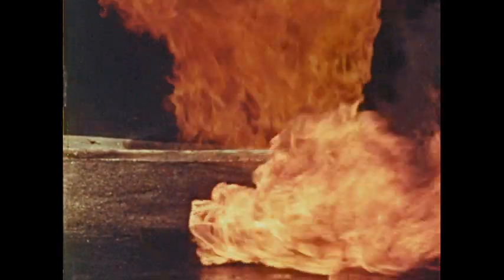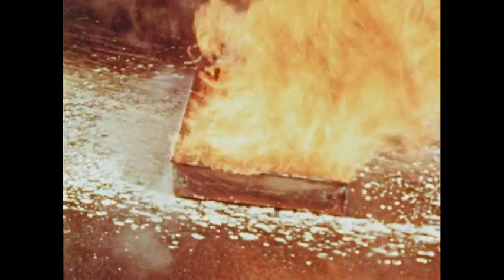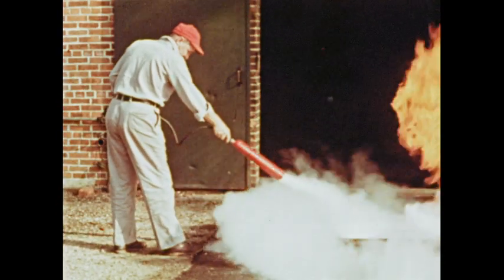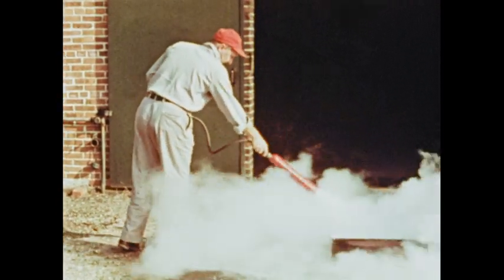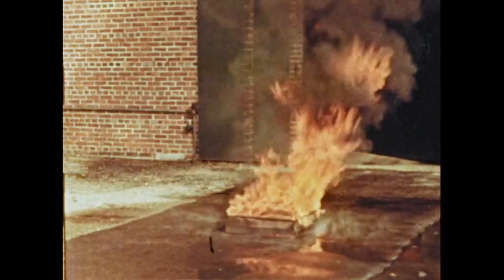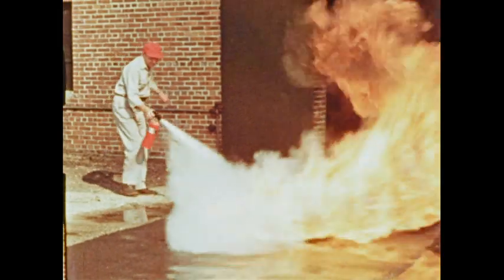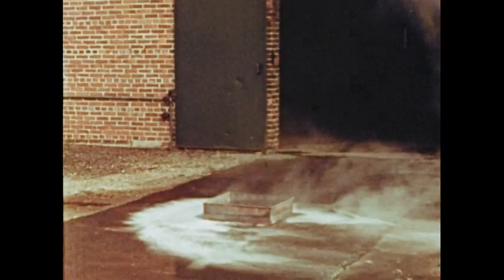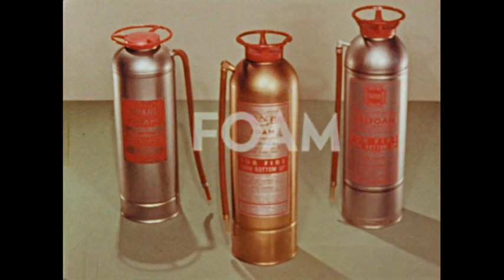There are three types of extinguishers that can be used effectively on flammable liquid fires. One is foam, which spreads a blanket over the burning surface and smothers the fire. Another good extinguisher is carbon dioxide, which reduces the oxygen content in the air below the point necessary for combustion. A third extinguisher good for flammable liquid fires is the dry chemical type, which discharges a cloud of dry, inert powder. So remember, for flammable liquid fires, there are three recommended types: foam, carbon dioxide, and dry chemical.